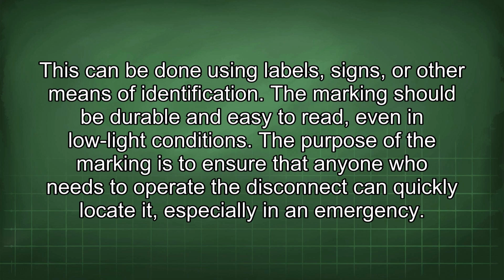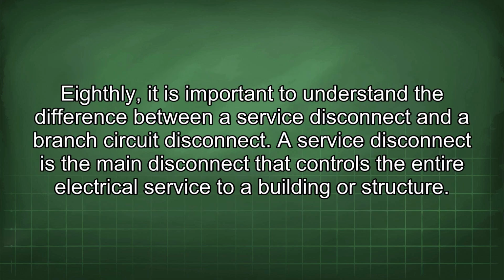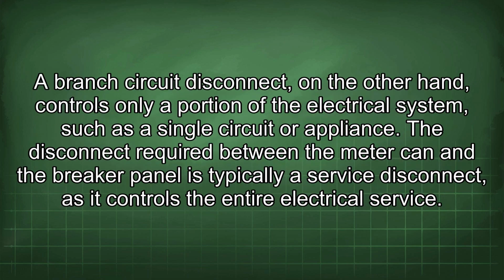Eighthly, it is important to understand the difference between a service disconnect and a branch circuit disconnect. A service disconnect is the main disconnect that controls the entire electrical service to a building or structure. A branch circuit disconnect, on the other hand, controls only a portion of the electrical system, such as a single circuit or appliance. The disconnect required between the meter can and the breaker panel is typically a service disconnect, as it controls the entire electrical service.